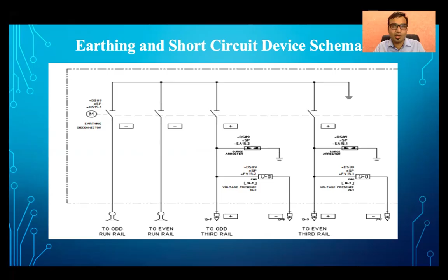In Kanpur Metro, we are using two types of earthing and short circuit device. One is the 4-pole system, which we are using on the main line. Another one is the 2-pole system, which we are using in depots. In the case of the typical 4-pole earthing and short circuit device, we are connecting all the running rails as well as the third rails to a common bus through cables, which is further earthed to the system.